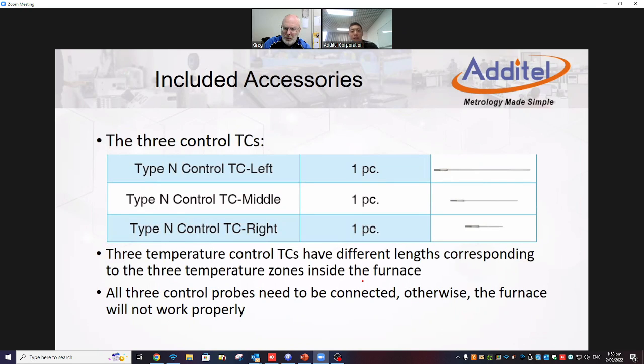So the accessories being included: the first one will be the 3 different length thermocouples. These are the control sensors. This is not a reference sensor. For the control sensors, we do have an accuracy spec, that's 5 degrees Celsius. So if the customer really wants to use the display number as a reference, no problem. But the problem is it is not accurate enough.